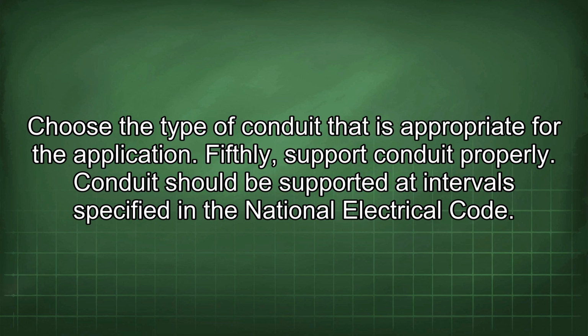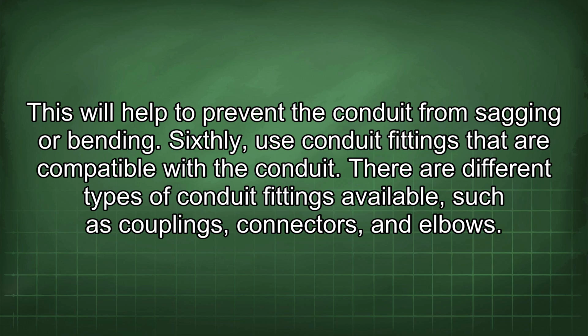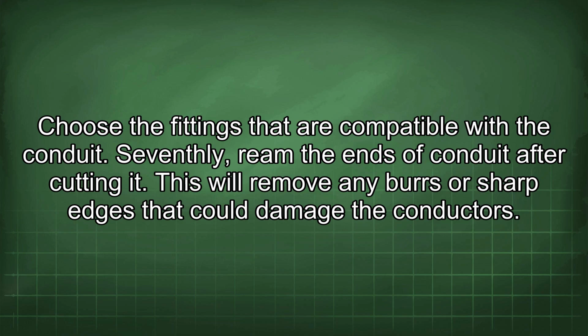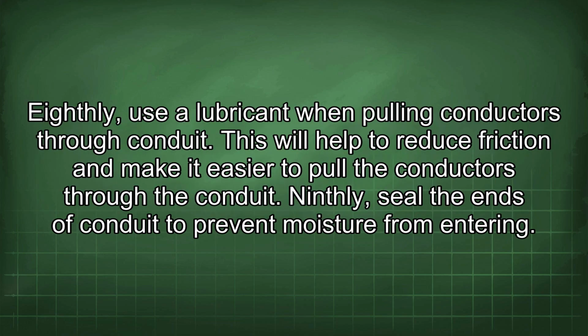Fifthly, support conduit properly. Conduit should be supported at intervals specified in the National Electrical Code. This will help to prevent the conduit from sagging or bending. Sixthly, use conduit fittings that are compatible with the conduit. There are different types of conduit fittings available, such as couplings, connectors, and elbows. Choose the fittings that are compatible with the conduit. Seventhly, ream the ends of conduit after cutting it. This will remove any burrs or sharp edges that could damage the conductors. Eighthly, use a lubricant when pulling conductors through conduit. This will help to reduce friction and make it easier to pull the conductors through the conduit.